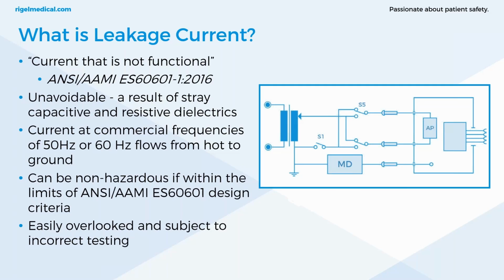So, leakage current that is non-functional. ANSI/AAMI ES 60601-1:2016 is derived from the international standard IEC 60601. In the US, ANSI/AAMI is used for electrical safety testing at the medical device manufacturer level. This is not at the service level, the BMET level. That is a different standard entirely, but it's all derived from IEC 60601.